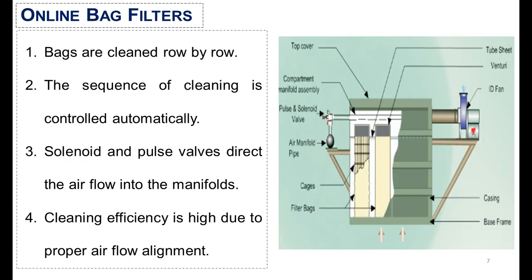Online bag filters are cleaned row by row and the sequence of cleaning is controlled automatically. For this purpose, solenoid and pulse valves are used. The cleaning efficiency of online bag filters is high due to the proper air flow alignment with the bag housing.